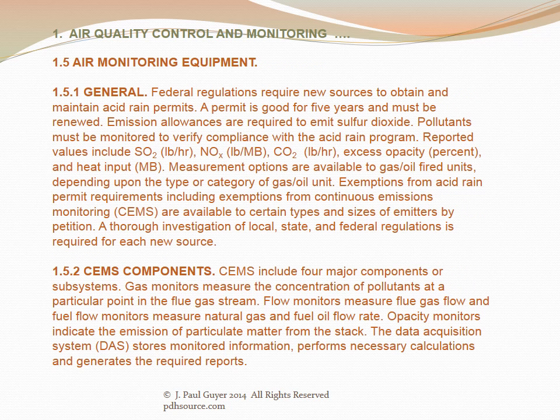Federal regulations require new sources to obtain and maintain acid rain permits. A permit is good for five years and must be renewed. Emission allowances are required to emit sulfur dioxide. Pollutants must be monitored to verify compliance with the acid rain program. Reported values include SO2 pounds per hour, NOx pounds per 1000 BTUs, CO2 pounds per hour, excess opacity in percent, and heat input in 1000 BTUs.